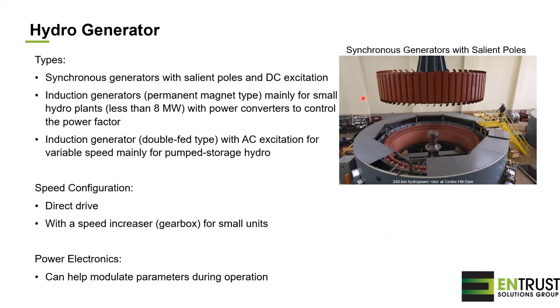Another kind of generator that we find mainly for small hydro plants is an induction generator of the permanent magnet type. Usually it's for projects of less than 8 megawatts. It requires, however, a power converter to better control the power factor. And now with the new technology that has been implemented mainly for pumped storage hydro, we will find an induction generator, double fed type, with AC excitation. So in this case, we need a lot of copper on the face of the rotor to be able to have this AC excitation.